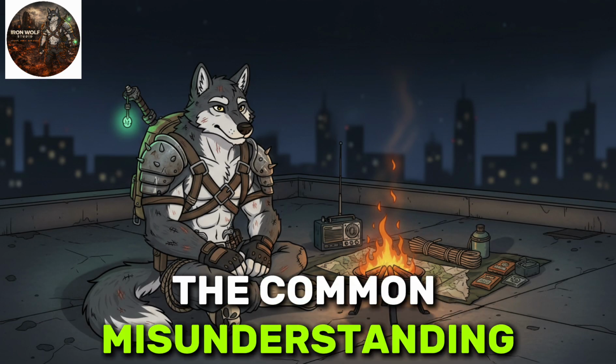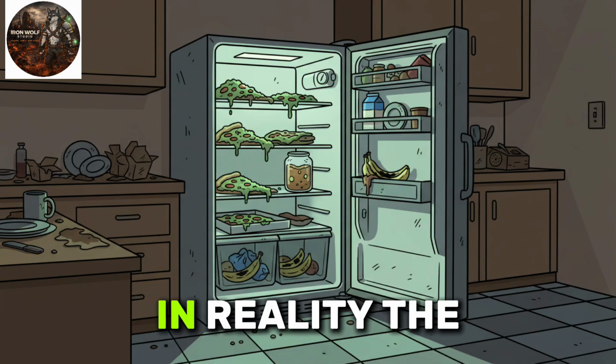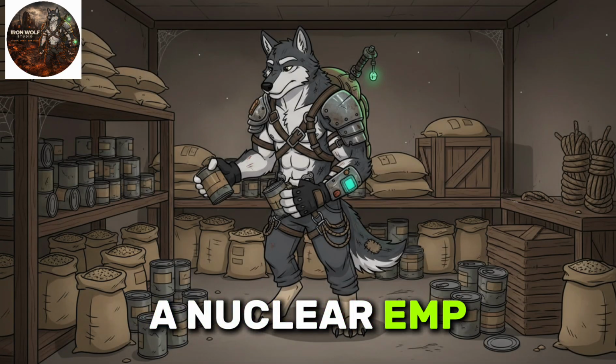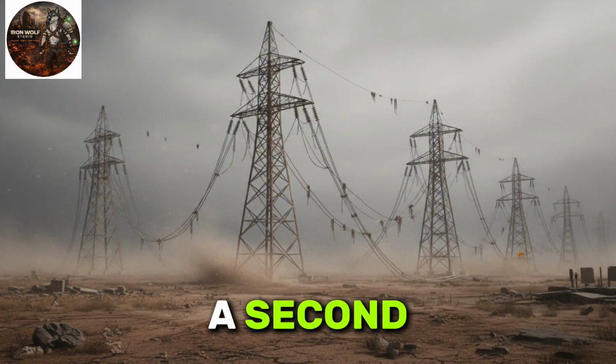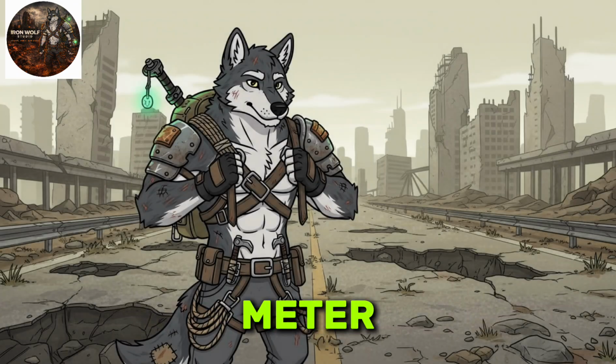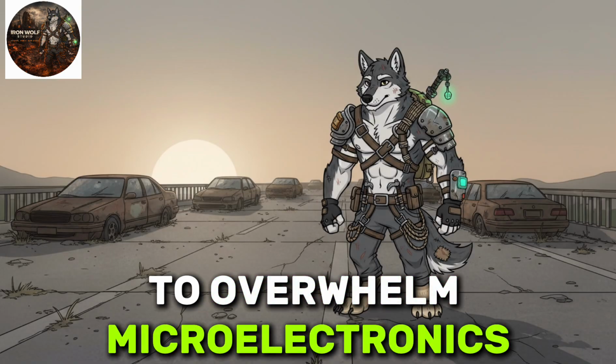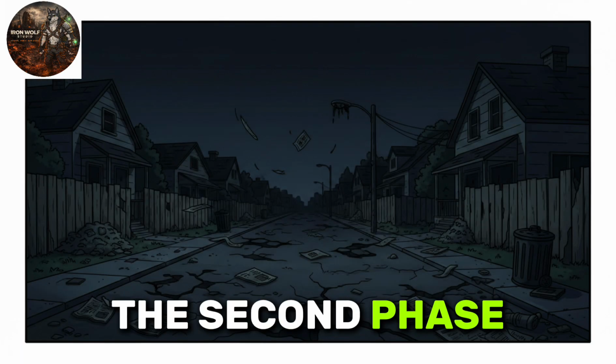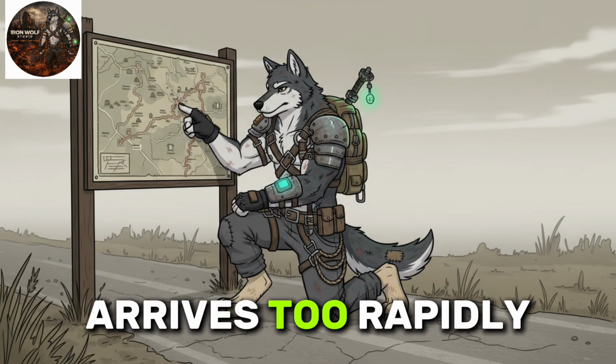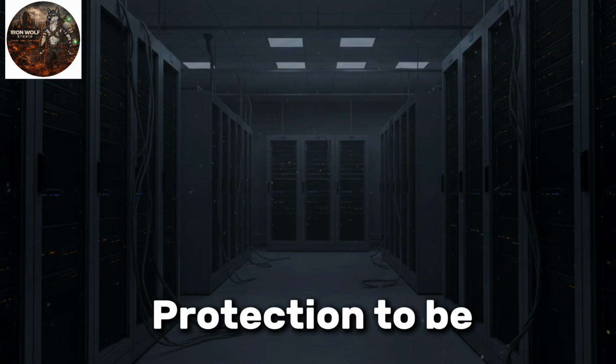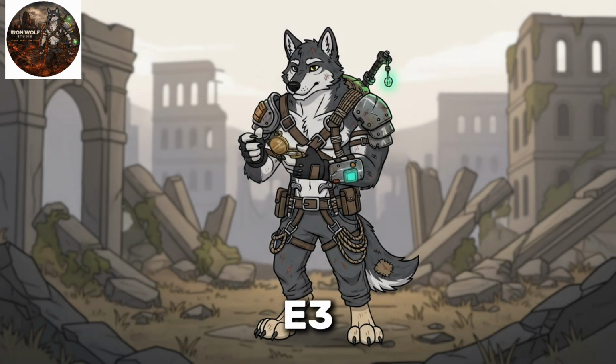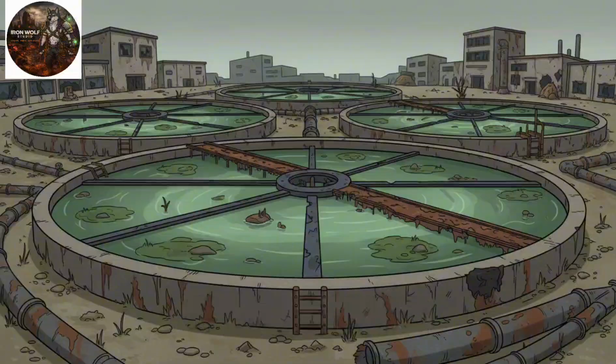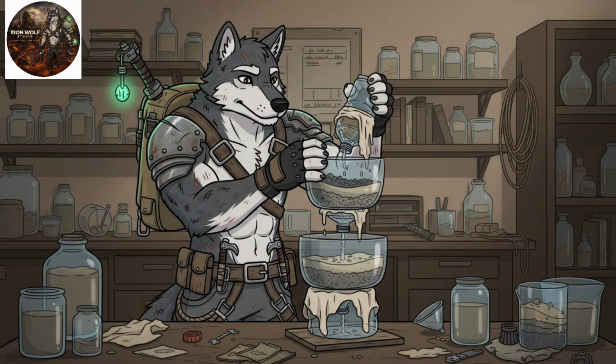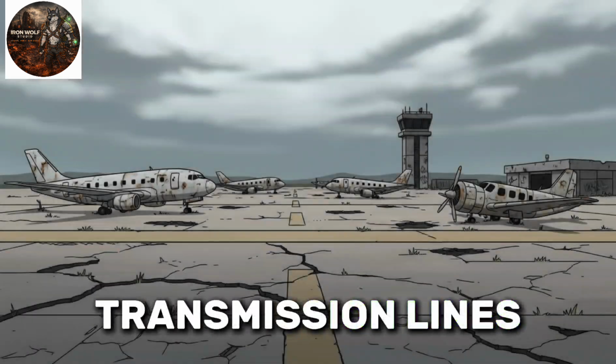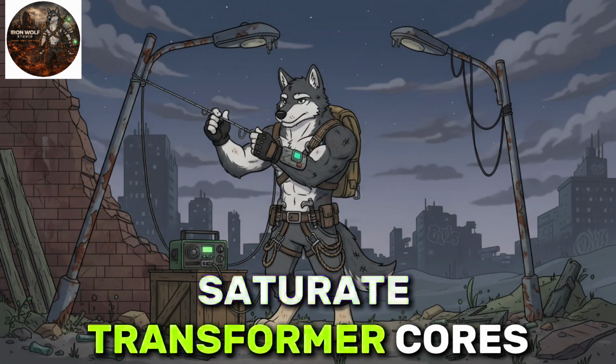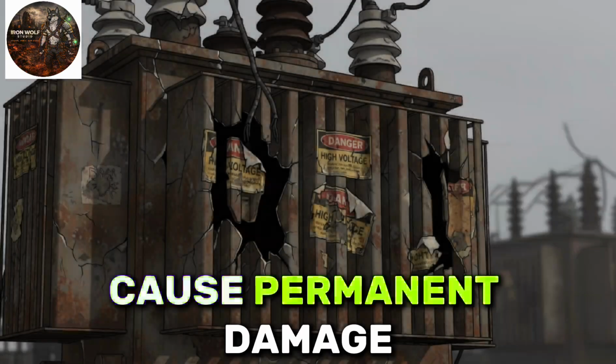The common misunderstanding is that such an event merely turns off electronics. In reality, the initial phase of a nuclear EMP, known as E1, lasts billionths of a second, yet can reach tens of thousands of volts per meter. That is enough to overwhelm microelectronics before protective devices react. The second phase, E2, resembles lightning, but arrives too rapidly after E1 for standard surge protection to be effective. The third phase, E3, unfolds over seconds to minutes and drives geomagnetically induced currents into long conductors like high-voltage transmission lines. Those currents can saturate transformer cores, overheat windings, and cause permanent damage.